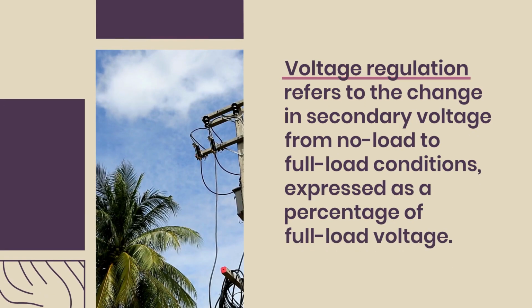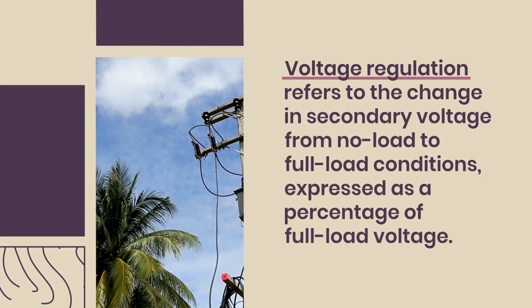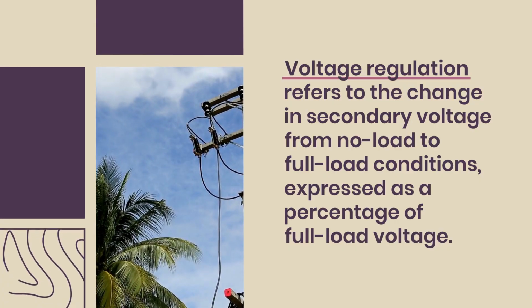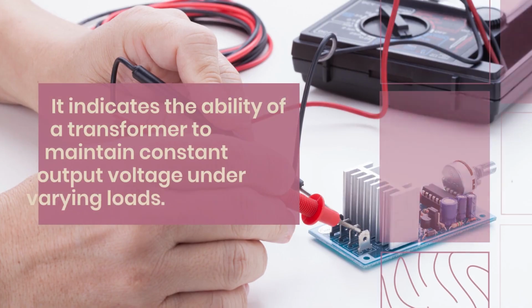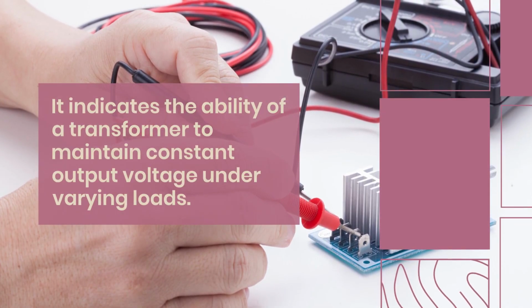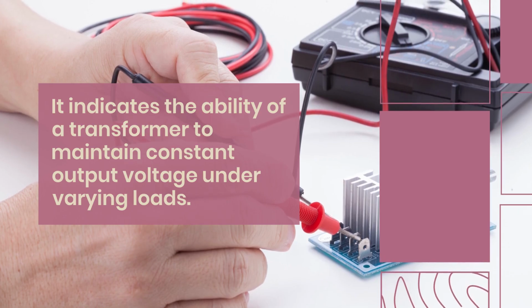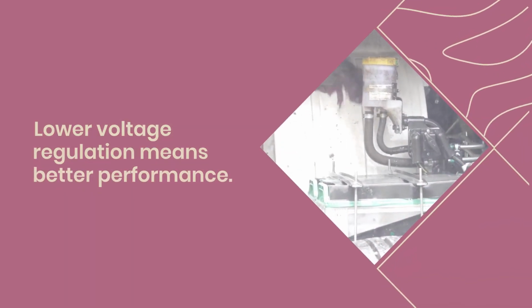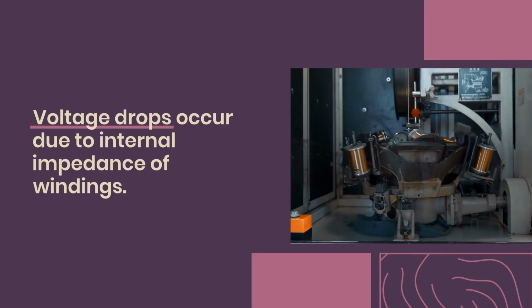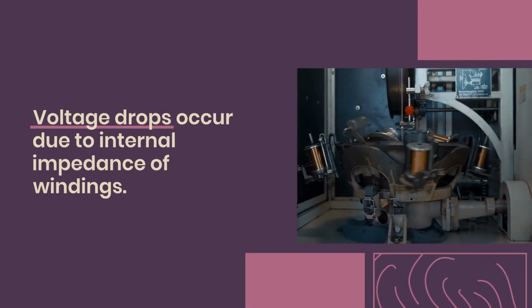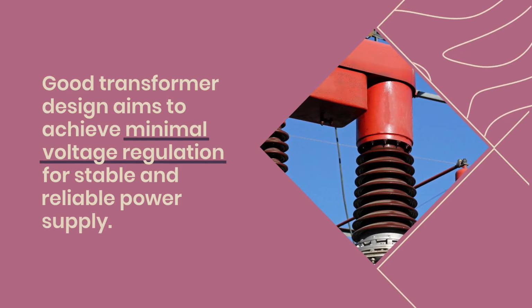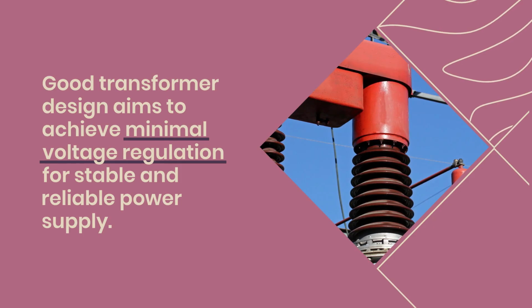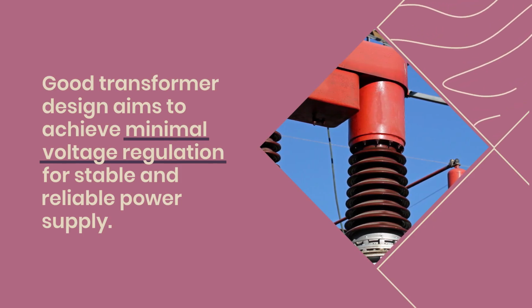8. What is voltage regulation in transformer? Voltage regulation refers to the change in secondary voltage from no load to full load conditions, expressed as a percentage of full load voltage. It indicates the ability of a transformer to maintain constant output voltage under varying loads. Lower voltage regulation means better performance. Voltage drops occur due to internal impedance of windings. Good transformer design aims to achieve minimal voltage regulation for stable and reliable power supply.